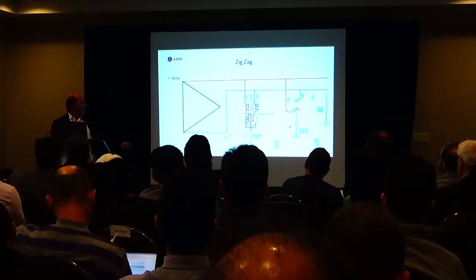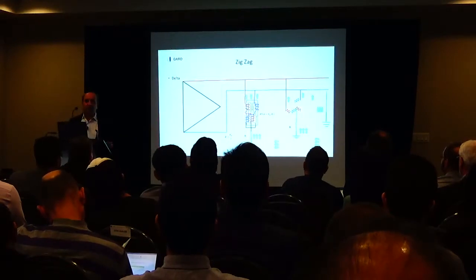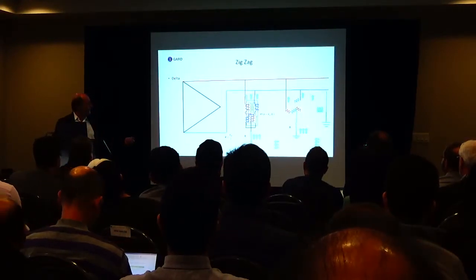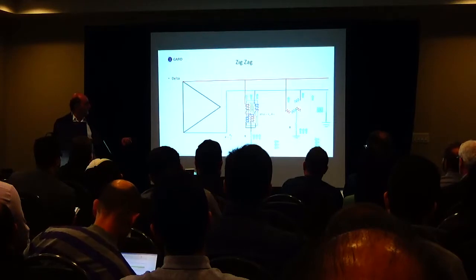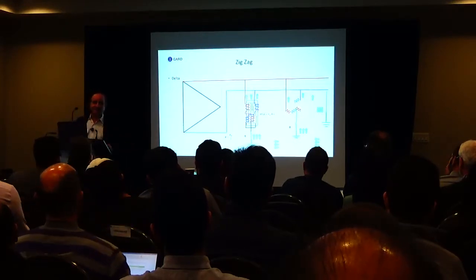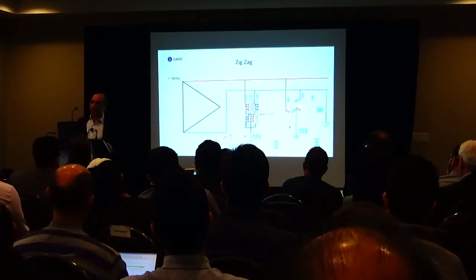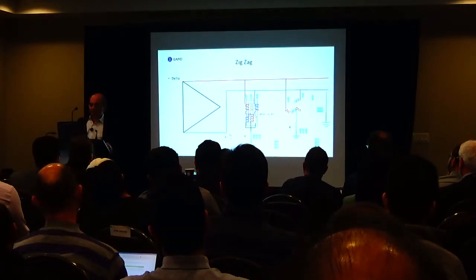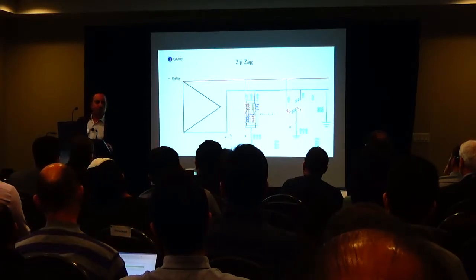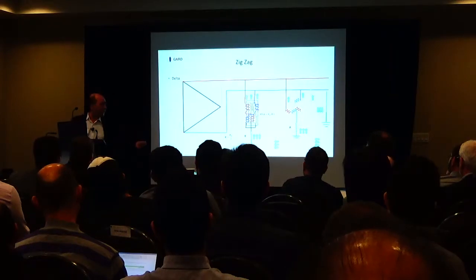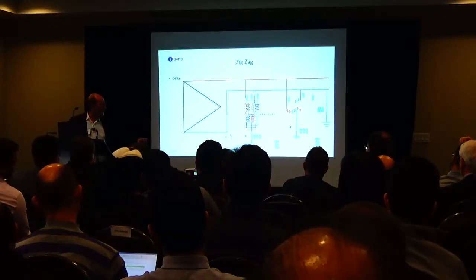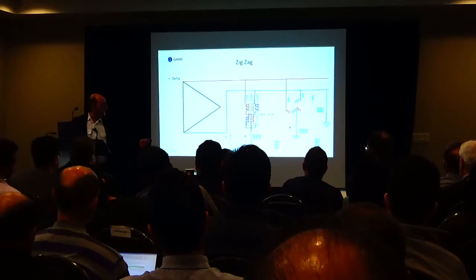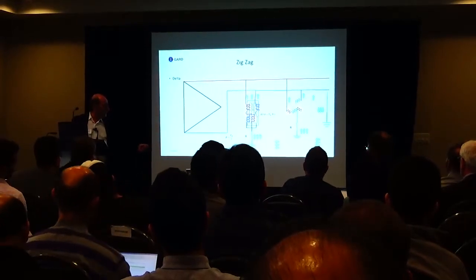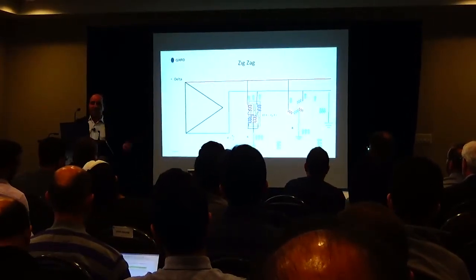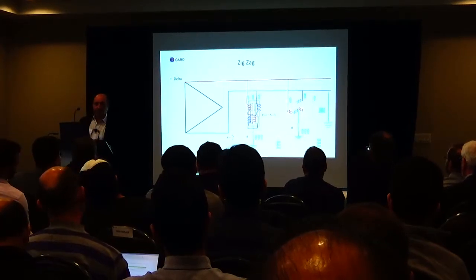If you want to convert your ungrounded system to a resistance grounded system, you can do it very easily by using a zigzag transformer. A zigzag transformer is designed in such a way that under normal system conditions, you have a high impedance device. Very, very low current flows through the zigzag. But when you have a ground fault, this is the mechanical and this is the electrical. So when you have a ground fault, the current goes through the zigzag back to the phases. So it's returning back to the source.